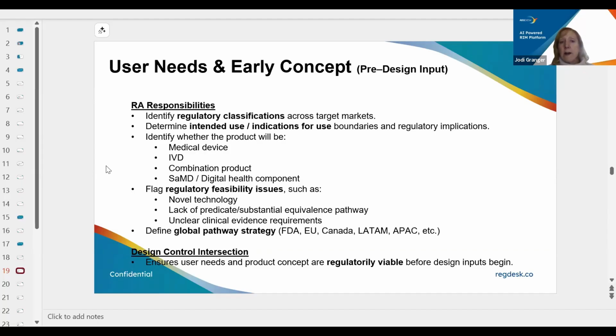The regulatory team will also identify for each market, is this actually a medical device? Is it an IVD? Does it fall into the classification for a combination product because perhaps we have a drug component on the device, like a drug-eluting stent? Is there software? And if so, does it classify as software as a medical device? So identifying for each market where your product is going to fall into these categories is very important. Not all products are considered a medical device in every single market. There are cases where a particular product is not classified as a medical device and therefore regulated much differently. So this assessment is really critical in these early concept phases.